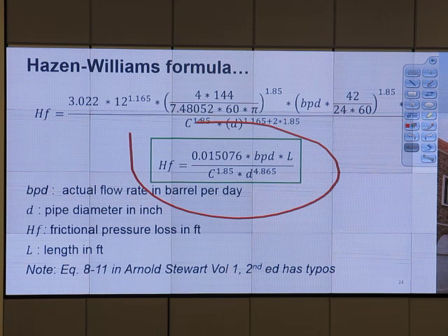So if you use oil and you get the same pressure drop as water, doesn't matter what kind of simulator they use, doesn't matter if he or she has a PhD, works 20, 30 years, you ask the question. You don't say they are wrong, but you say, okay, I did the same calculation for the water case, it gives me 20 psi. I use the Hazen-Williams equation, which is very easy and very difficult to make a mistake. Of course, you may make a mistake. And I get 20 psi.